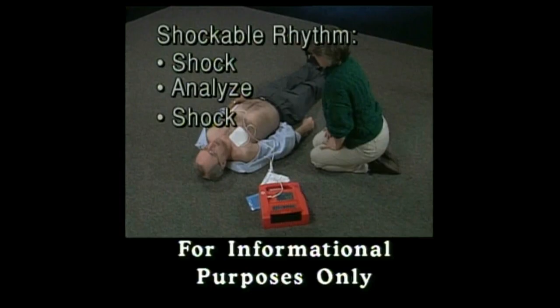After the second shock, the VivaLink analyzes the patient's cardiac rhythm again. Charging. If the patient still has a shockable rhythm, the VivaLink will charge again, and you will hear this prompt a third time. Stand clear. Push flashing button to rescue. Push the rescue button again to deliver a third shock. You don't need to be concerned about how many shocks or what strength shocks to give. The VivaLink is pre-programmed to deliver a series of 3 escalating shocks.